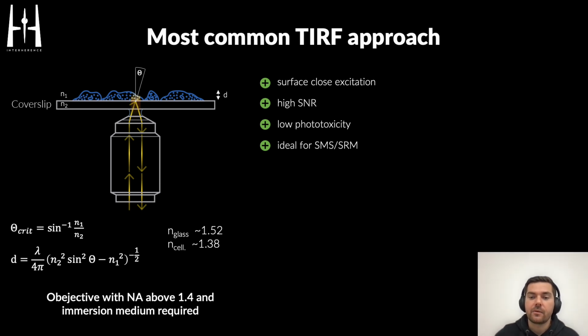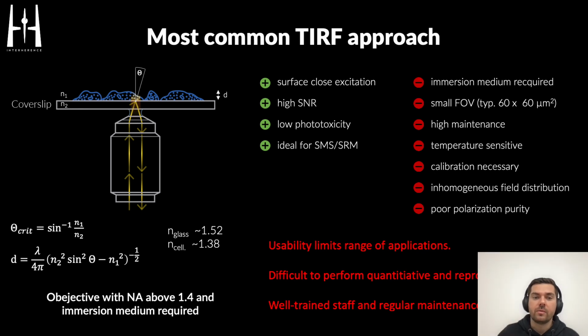But this technique itself comes with several drawbacks. These drawbacks include that you always require immersion medium in objective-based approaches to achieve the required numerical aperture of 1.4 that is needed to have the beam entering in the total internal reflection condition. This comes with a drawback that you have only very small fields of view of 60 by 60 or 100 by 100 micrometers. The systems often require high maintenance. They are temperature sensitive. By changing the temperature, you might lose your TIRF angle. The penetration depth usually needs to be calibrated if you want to do quantitative TIRF. You often suffer from inhomogeneous field distributions and poor polarization purity.